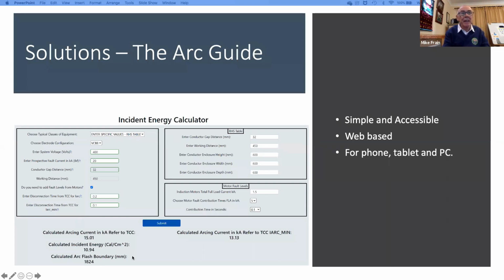These aren't finished yet, but this is a typical incident energy calculator. Normally these two boxes aren't shown. This is all you need. You can choose electrode configurations there on your right hand side. And all the voltage, this particular case is based on IEEE 1584, goes up to 15,000 volts. And it went to disconnection times within that panel there.